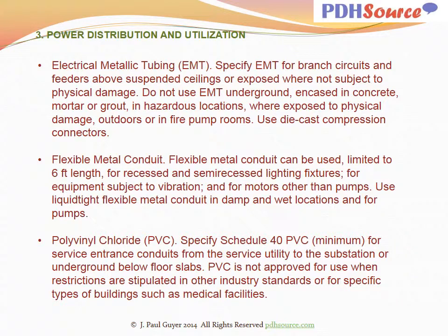Electrical metallic tubing, EMT: specify EMT for branch circuits and feeders above suspended ceilings or exposed where not subject to physical damage. Do not use EMT underground, encased in concrete, mortar, or grout, in hazardous locations where exposed to physical damage, outdoors, or in fire pump rooms. Use die-cast compression connectors.